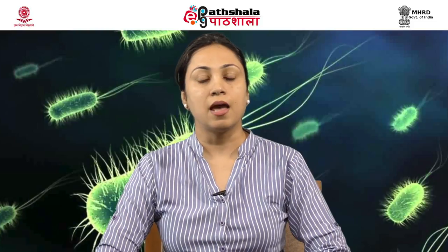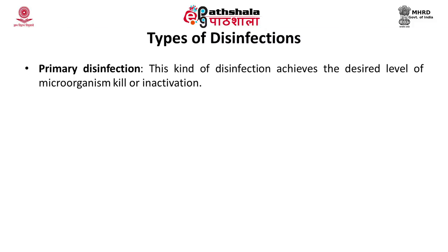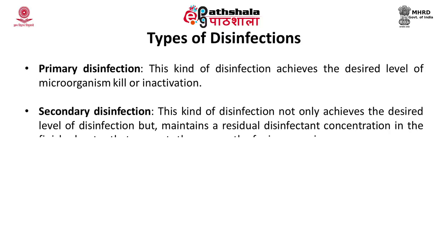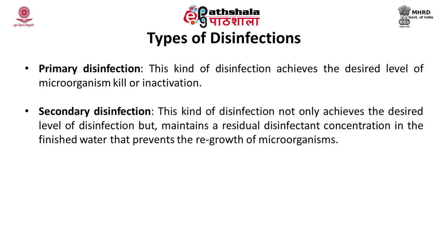There are two kinds of disinfectants: primary disinfectants and secondary disinfectants. Primary disinfection achieves the desired level of microorganism kill or inactivation, while secondary disinfection not only achieves the desired level of disinfection but also maintains a residual disinfectant concentration in the finished water, which prevents the regrowth of microorganisms.